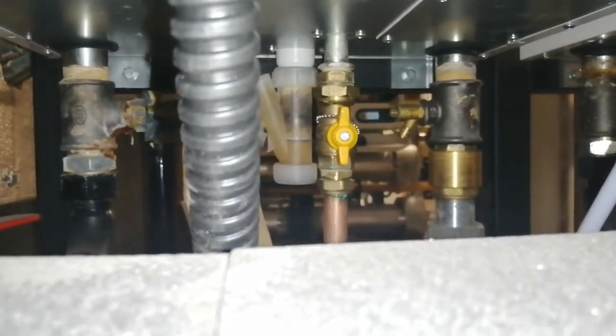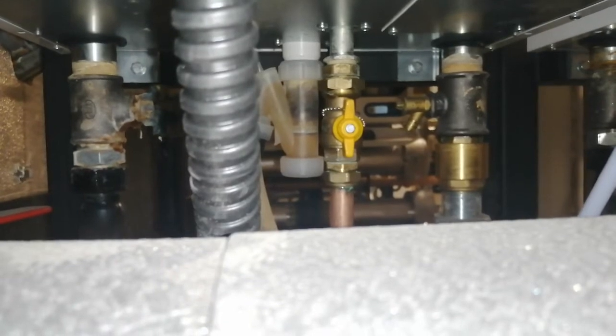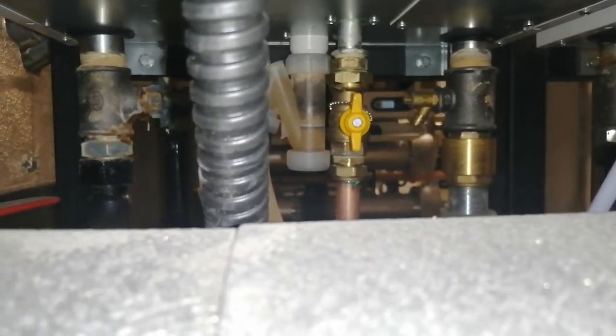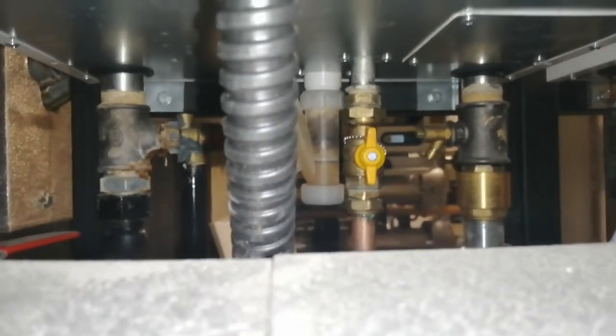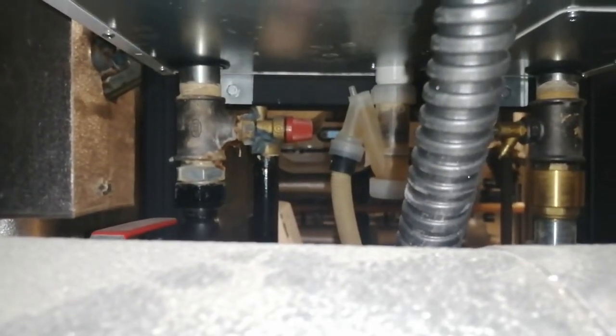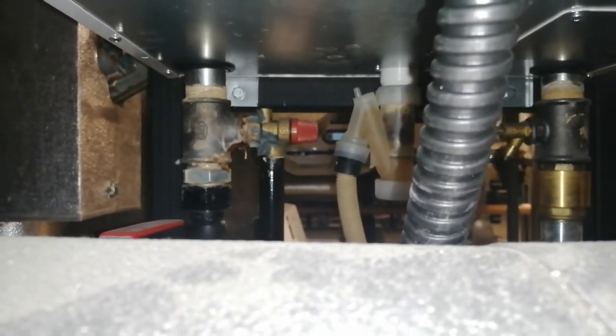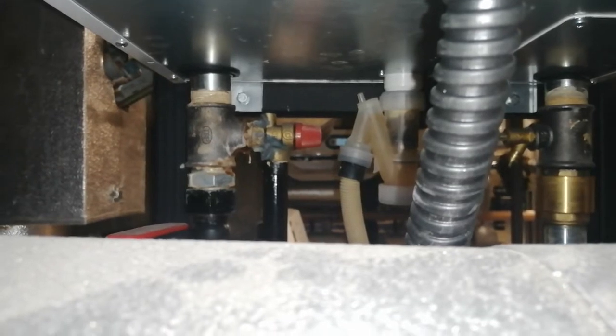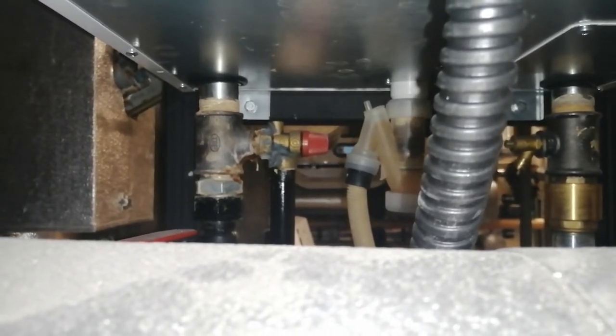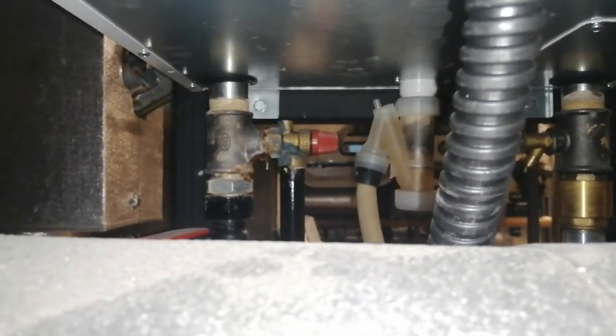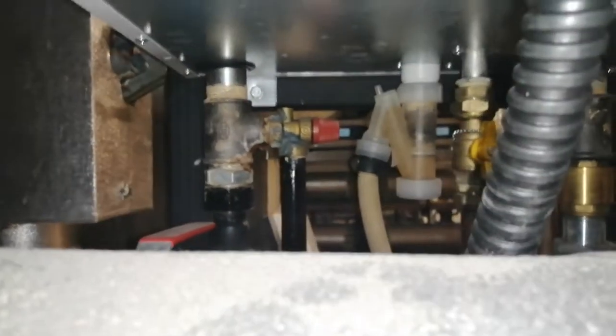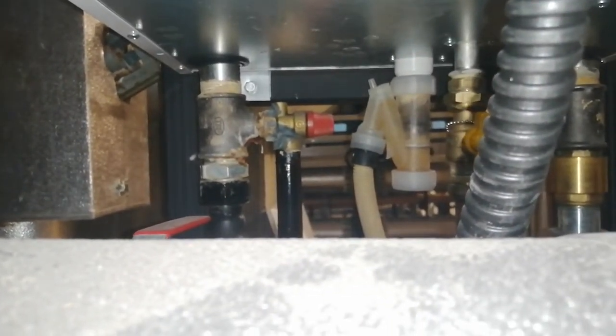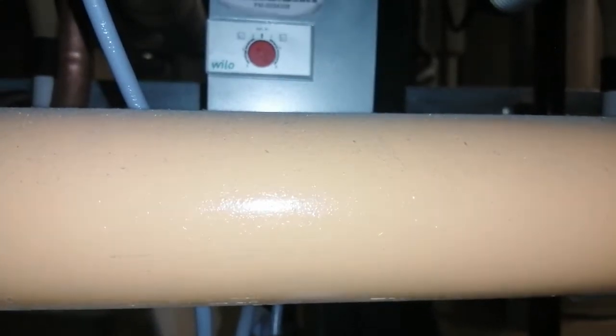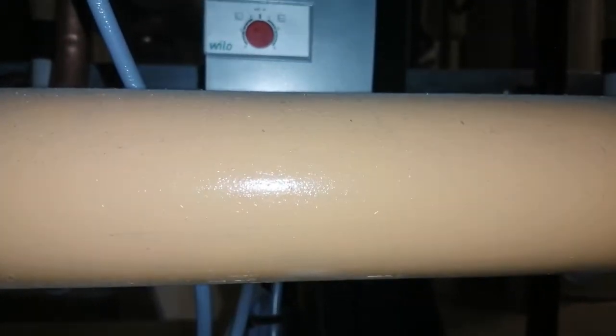Check that your gas pipe, your gas supply, is labelled and clipped throughout the run. Check your PRVs that they're in date. I believe they should be 5 years old max. That should be the date on them. Some of them you can't find a date, but ideally every 5 years these pressure relief valves should be changed. Check that your pump is running. I have a pump here underneath this boiler. I want to make sure that it is operating.